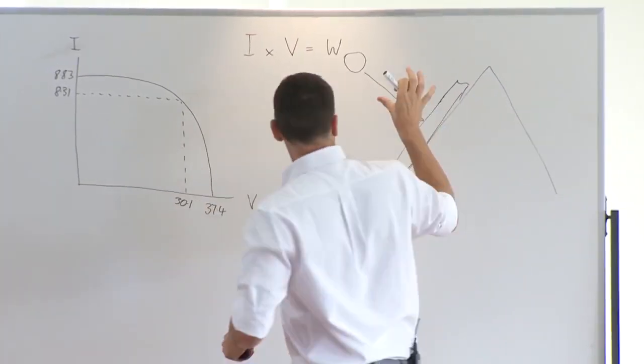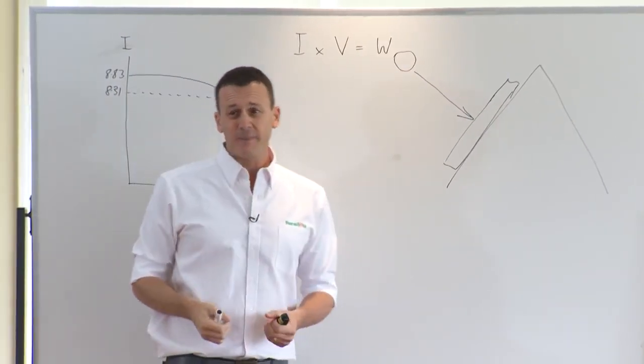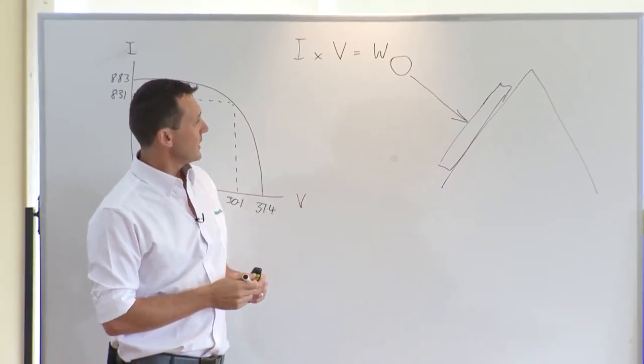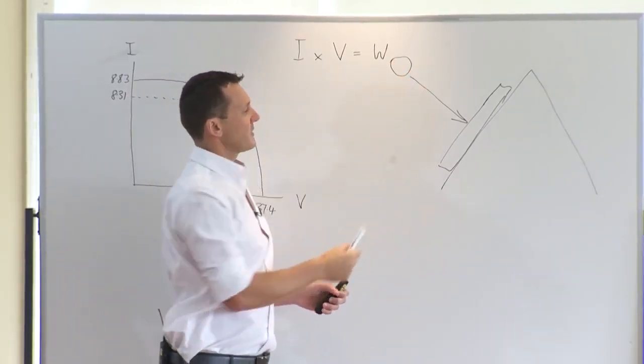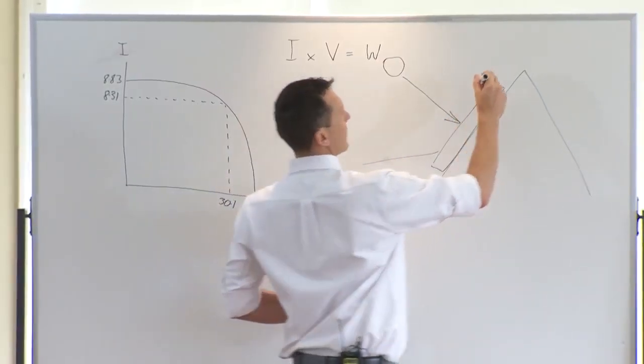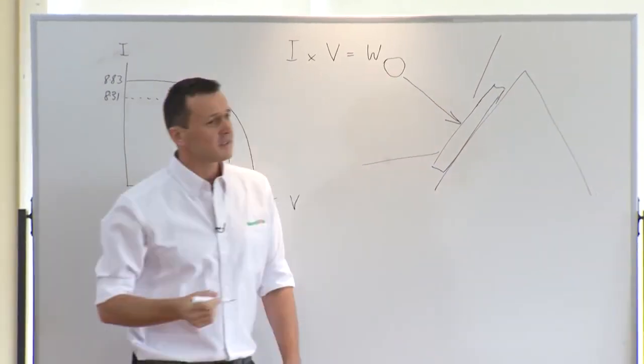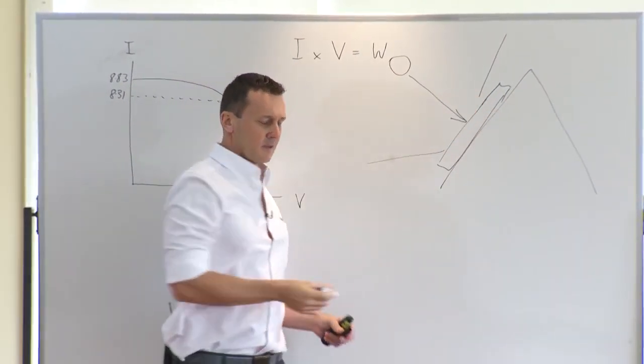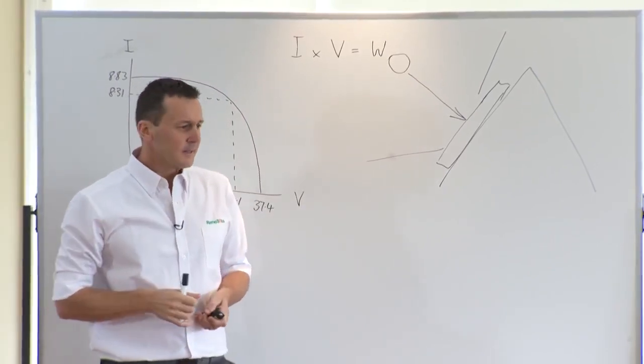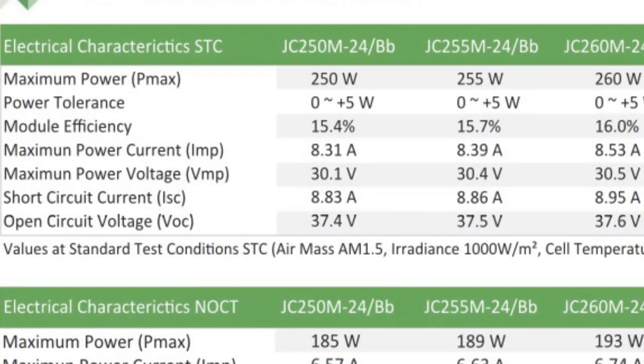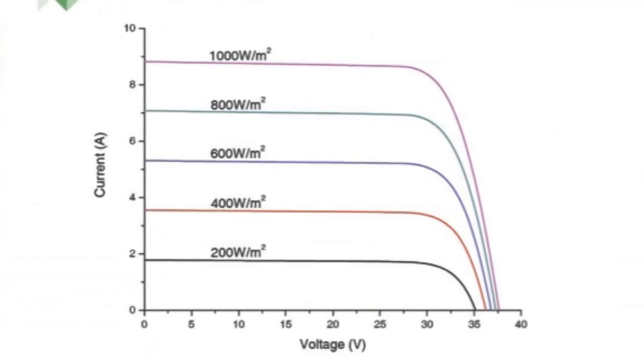But of course, as we all know, the sun doesn't sit at that position perpendicular to our panels all day. What we would normally see is the sun varying across the day, potentially being at low angles here to higher angles or higher positions, but giving us a lower angle relative to the module. And on that data sheet, you'll see a curve for the different irradiance figures. The lowest one being at 200 watts per square metre, and leading up to that 1000 watts per square metre, which is your most ideal position here at 90 degrees.